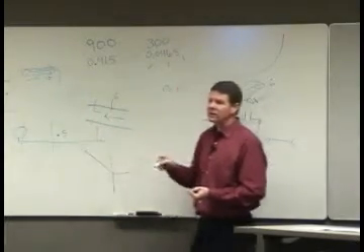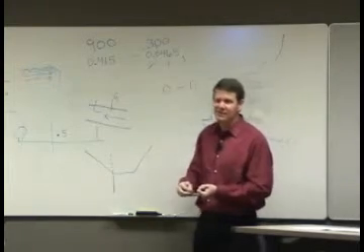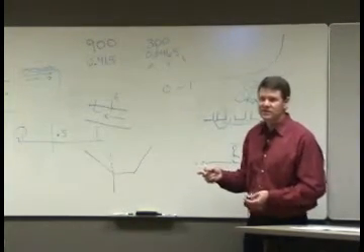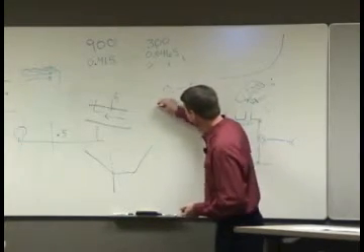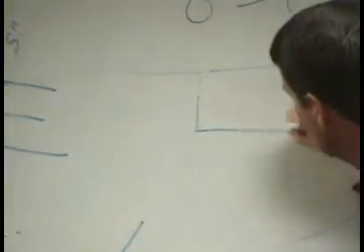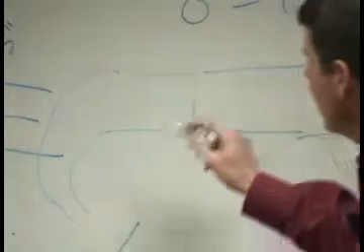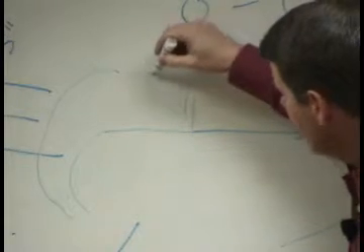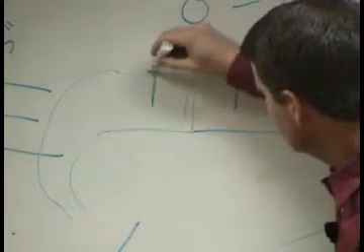Andover uses a hot wire anemometer type of device for their airflow sensor. You hook your plastic on each end, going off to the two tubes on your pitot, and they have a tiny heater and a tiny temp sensor and an orifice in there.